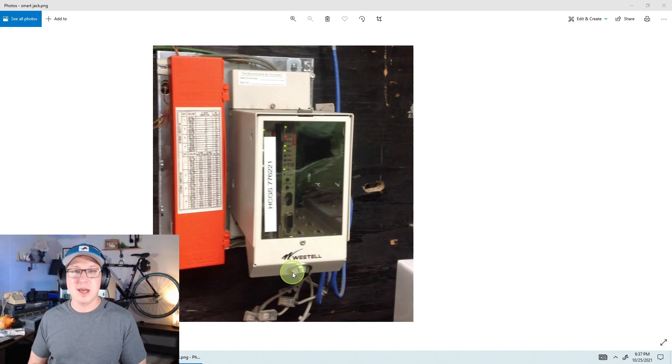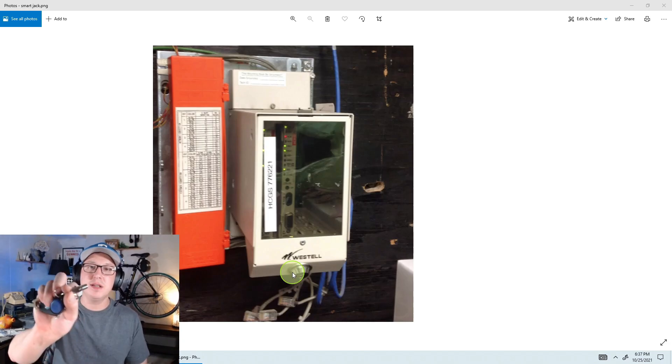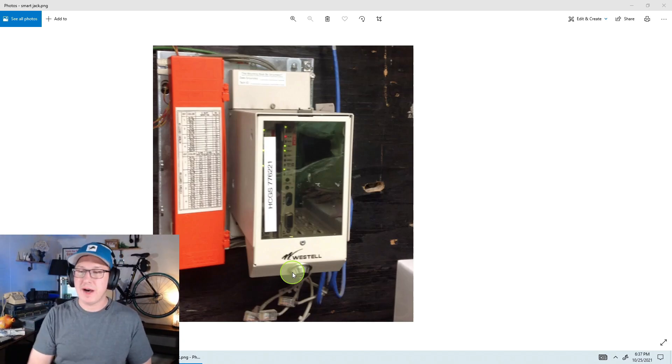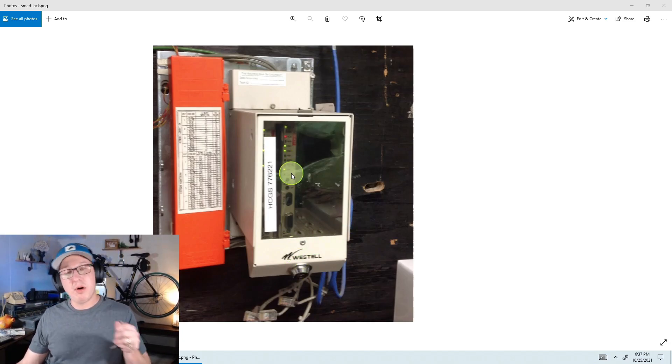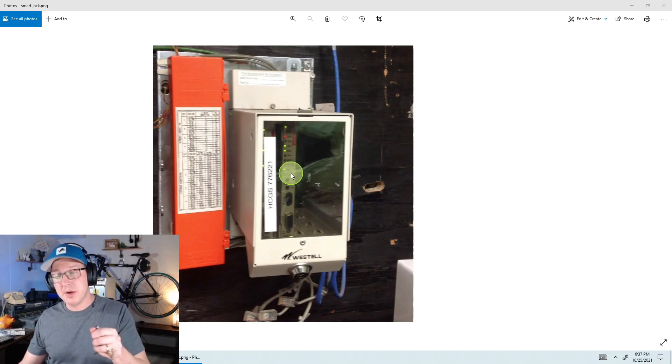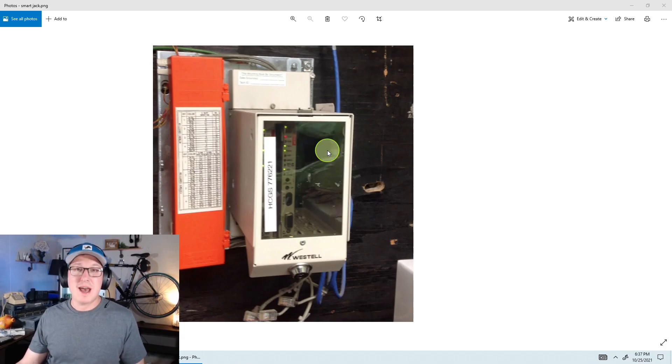So this key, if you can get one, they're pretty universal. I have one on my keychain. So if you can find one, you'll be able to open this up. And then if your circuit is not working, you can pull the card out and then push it back in. It has these little indicator lights on it. If you're getting a red light on one of these, then you know there could be a fault.